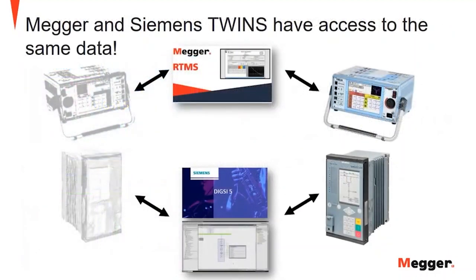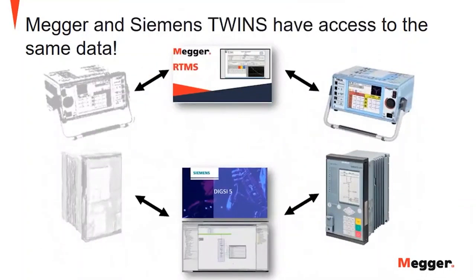So the Megger twin and the Siemens twins actually have access to the same data. RTMS software takes a test file and can run it against a twin, or against a real test set. DIGSI can take an IEC file and run it against a relay twin or a physical relay. This is very important for easy virtual commissioning and for having the benefit of the results in the real world.